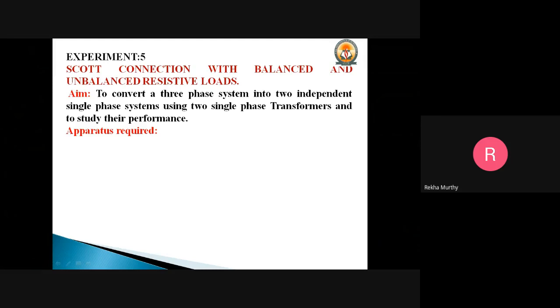The two ends of the main transformer and the 86.6% tapping on the teaser transformer will be connected to the three-phase supply on the primary circuit and to the load on the secondary side. We must ensure the current ratings of the two transformers are the same. By this arrangement, we can obtain two single phase supplies. This is how we perform the SCOTT connection.